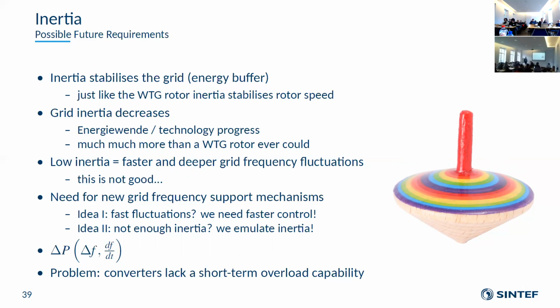But the grid inertia decreases much more than the wind turbine rotor inertia, because in this energy transition, many power stations just get replaced by solar panels that have zero rotating mass. So the grid inertia is really much more on the way down than the wind turbine rotor inertia would ever be able to go down. This low inertia can cause fast and deep fluctuations of the frequency, and this is not good. So this means we need to support the frequency in a different way than we have ever used before. Frequency support has existed for 100 years and it worked, but the old methods can't hold up to the future. Basically there are two ideas.